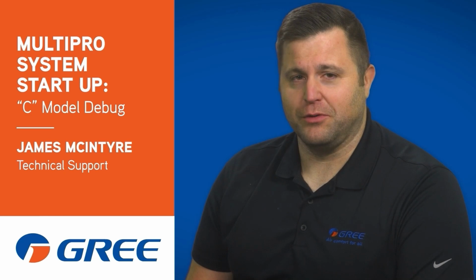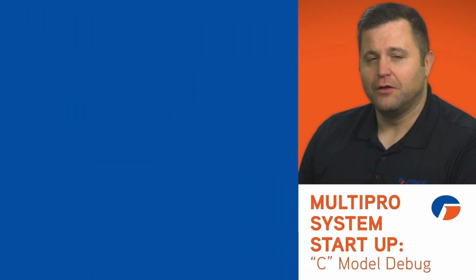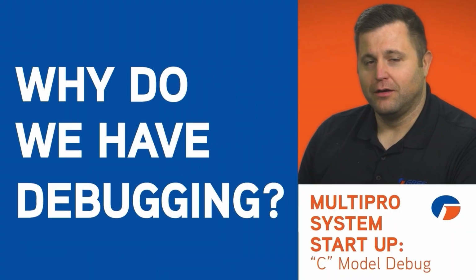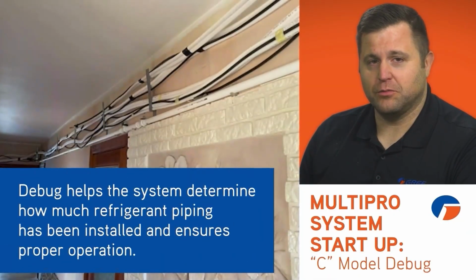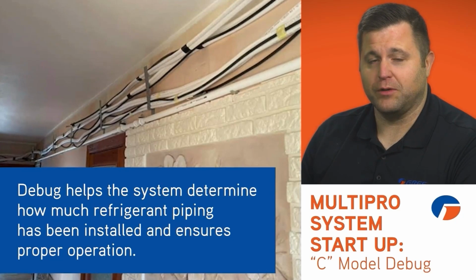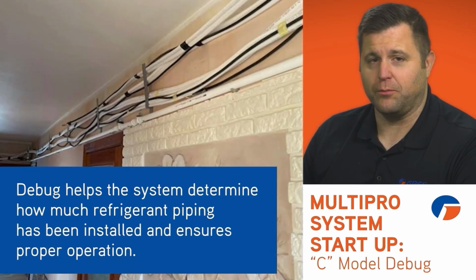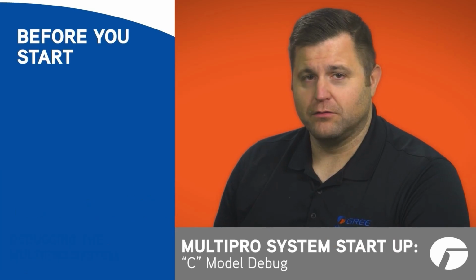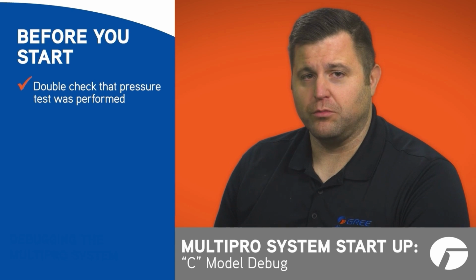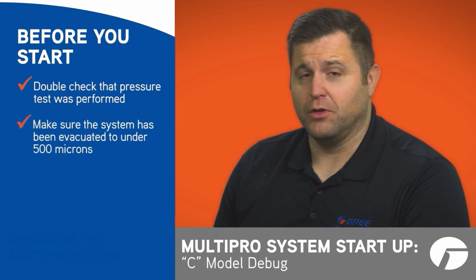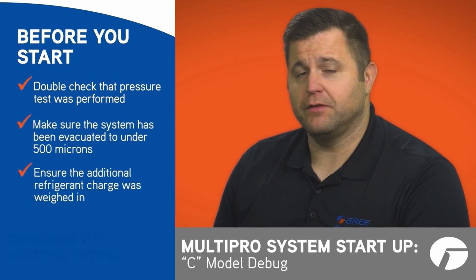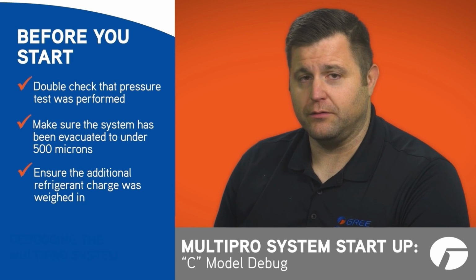Alright, now that your installation is complete, your MultiPRO system must go through a startup sequence also known as debugging. I'd like to walk you through the step-by-step process to ensure proper operation of the MultiPRO system. So why do we have debugging? Among other things, this process helps the system determine how much refrigerant piping has been installed and ensures proper operation. Before beginning, double check that a pressure test has been performed, the system has been evacuated to below 500 microns, and that the additional refrigerant charge was weighed in.